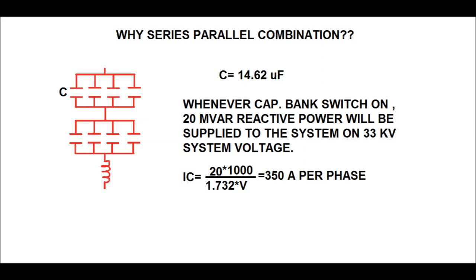The capacitor bank injects leading reactive power to improve the power factor of the system. The capacitive current injected per phase is IC = 20,000 / (√3 × 33 kV) = 350 ampere per phase. That is, whenever the capacitor bank is switched on, each phase carries a capacitive current of 350 ampere.